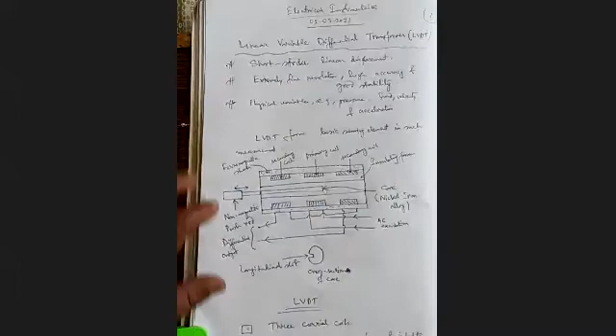Last point, this is very simple. When you slide the core through the inside, it is moving to and fro. The structure is fixed and the core is moving. So if the outer surface of the core touches the inner surface of the fixed structure, there is friction and rubbing. So there will be wear and tear of the material. So some bearings are connected throughout this entire thing. Linear bearing. Bearings are normally connected in a circular fashion, but this is in a linear fashion, along a length. It is called a linear bearing. So that will prevent direct contact between the fixed and moving structure.